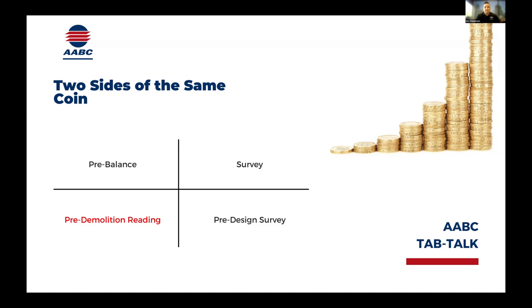Sometimes there are caveats the engineers want to see, if there are VAVs on the project. We've been asked before, can you open those VAVs 100% so we know the maximum amount of airflow we can get out of that VAV? Now that's at a given static, right? So if the air handler is operating at 1 inch of static, we want to know the maximum CFM at a damper position of 100 we can get out of it. So that's some information for them to help with the design.